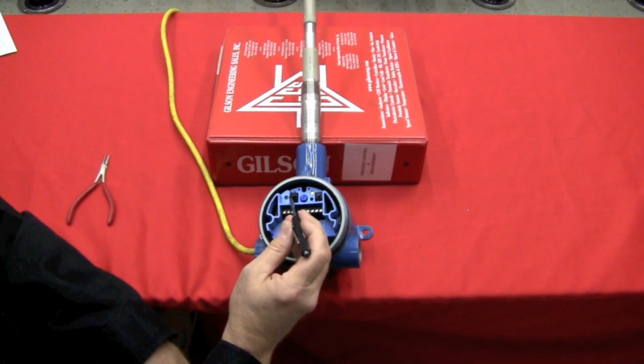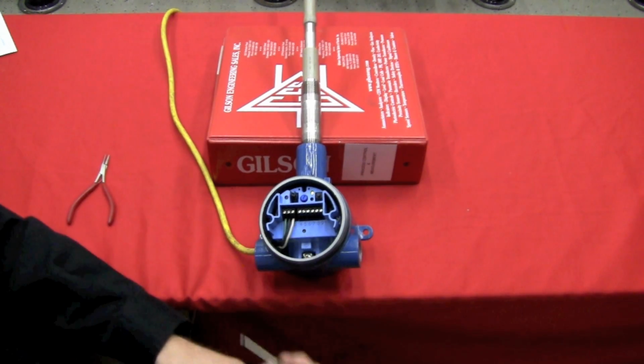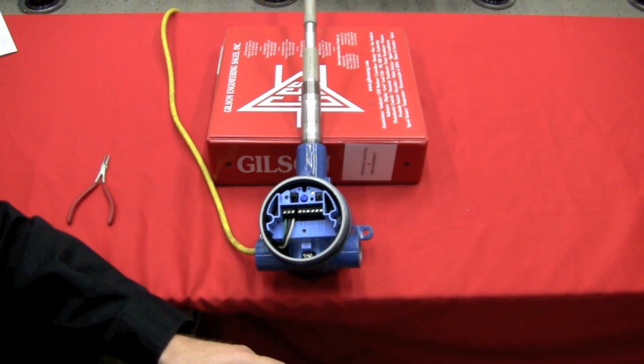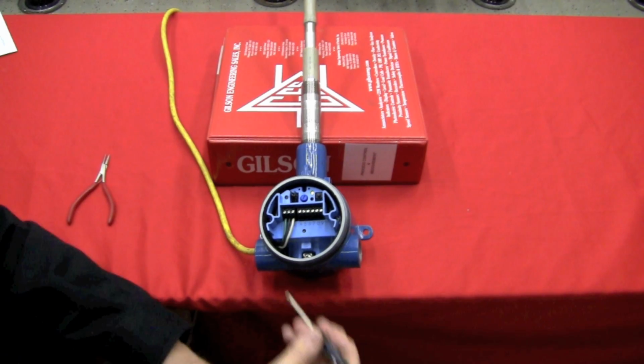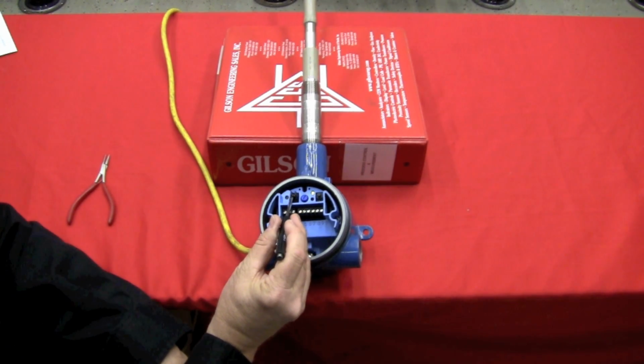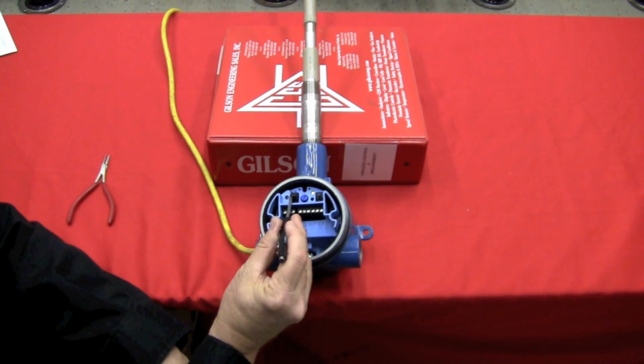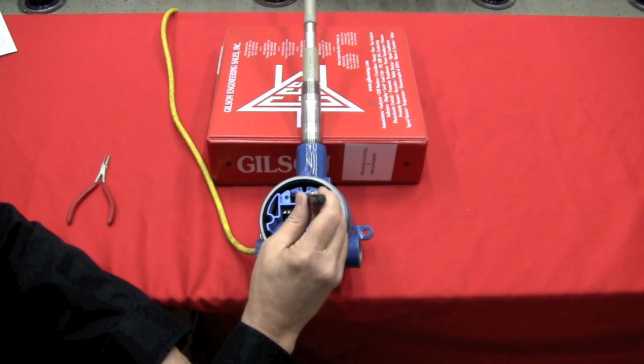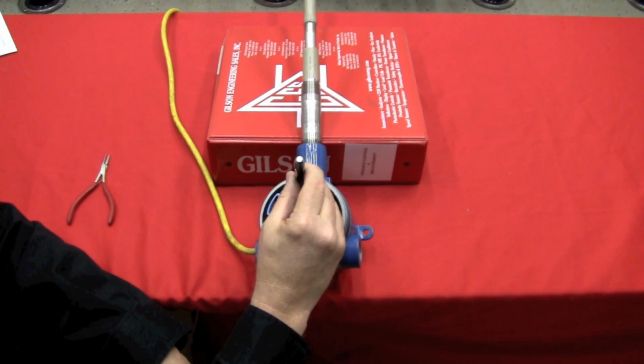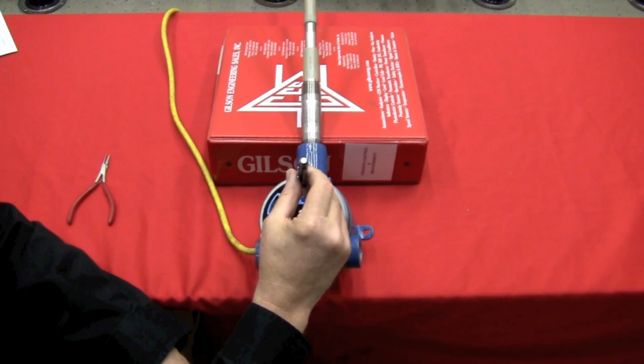Let me first explain this jumper on the left-hand side, which is our time delay jumper. We can put it in two different positions. One, we can delay the unit from going into alarm, or we can delay it coming out of alarm. I currently have it in the up position, which will delay it coming out of alarm. So if I go ahead and crank in a little bit of time delay, let's say that we had a process that was hugging right around our switch and we didn't want it to continually go in and out of alarm, I'll dial in a little bit of time delay.